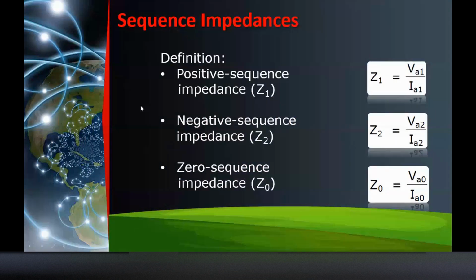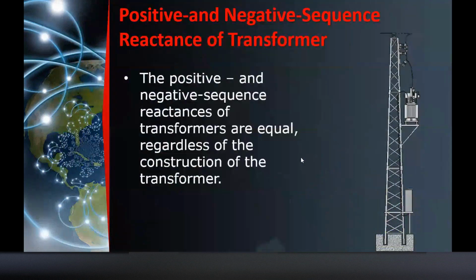Okay, dito naman is the positive sequence impedance. So the positive sequence impedance Z1, this is the formula. Negative sequence, nasa derivation naman yan, class. Makikita nyo pag pinasa ko sa inyo yung slide ko. For the transformer, tatandaan natin, positive, negative sequence of the transformer are equal regardless of the construction of the transformer. Meaning, kung ano yung makita mong positive sequence reactance, it's the same as negative. So kung 5% ang positive, definitely negative niya is 5 din. Okay? Yun yung tatandaan niyo.